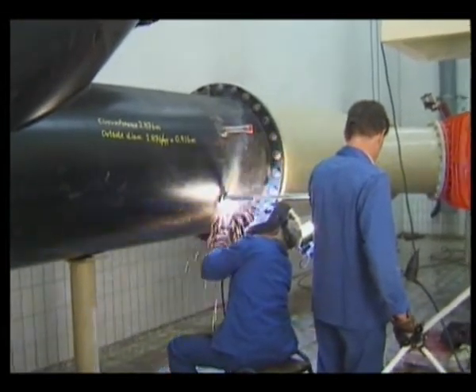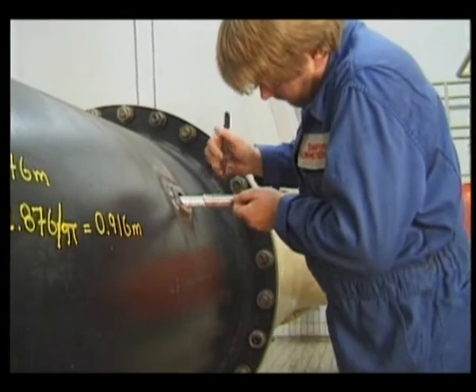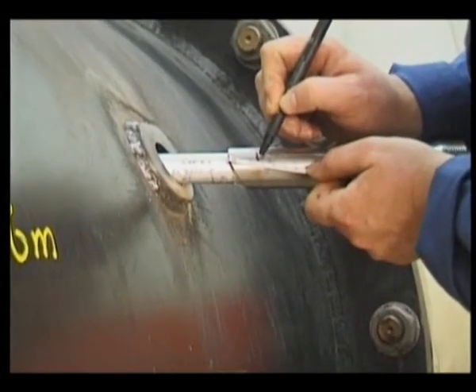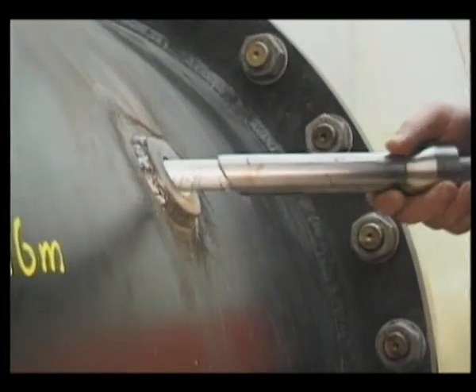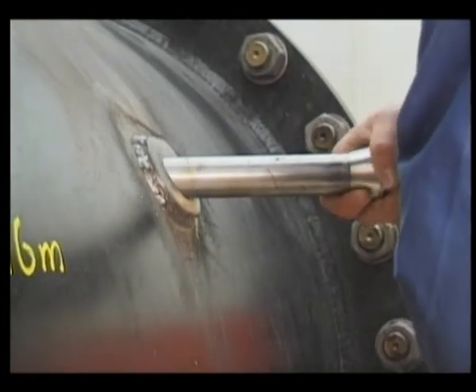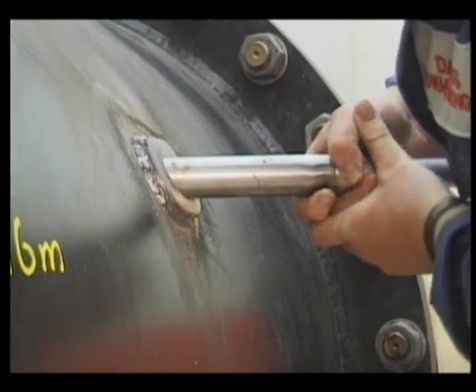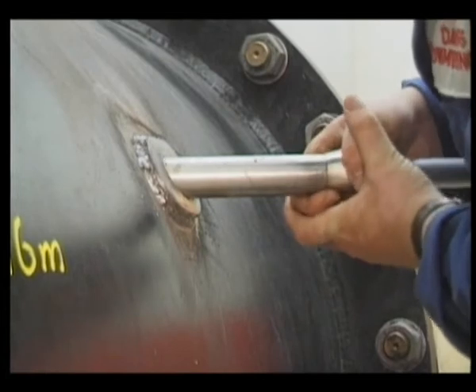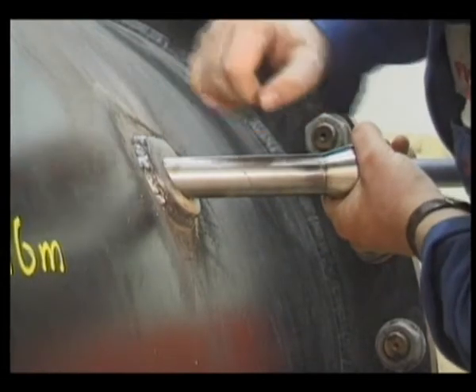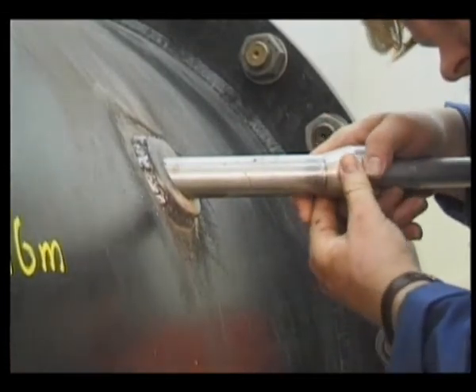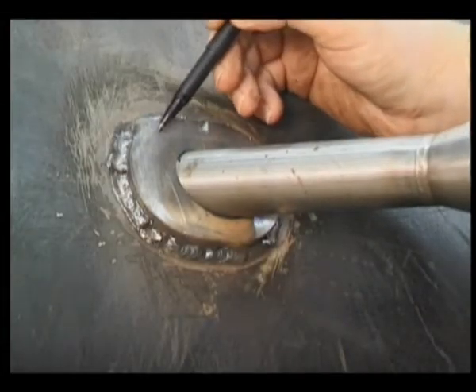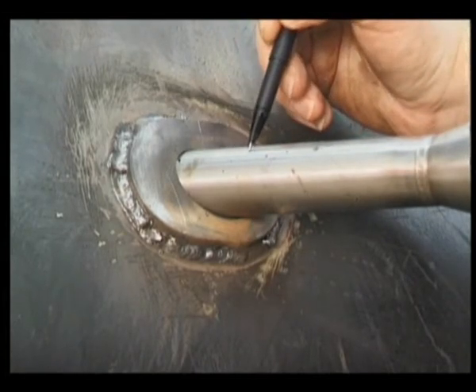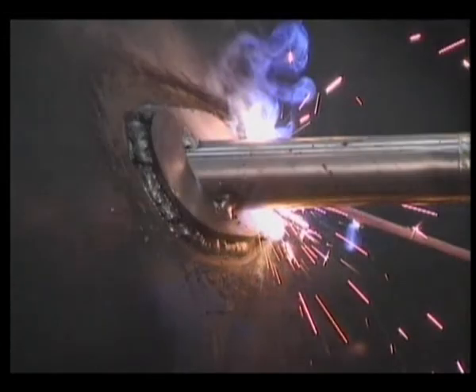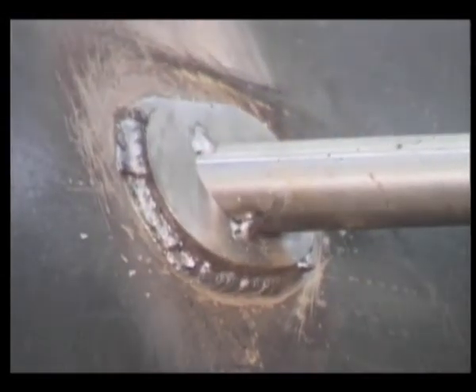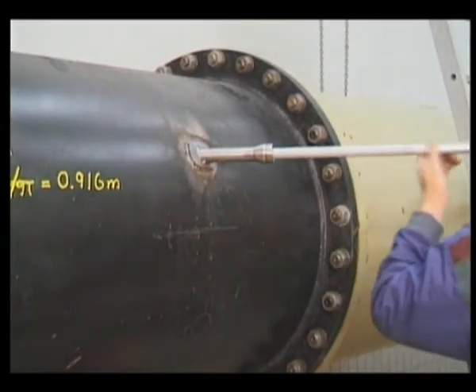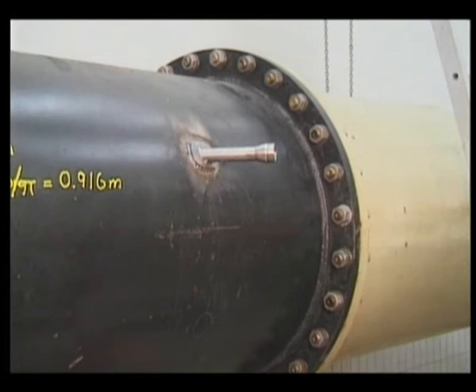The transducer holders must be led into the mounting plates and pipe until aligned with the internal pipe wall. To ensure this, a mark's drawn on the transducer holders. The diagonal line on the mounting plate must be aligned with the line on the transducer holders. Then the transducer holders are tack welded in 3 or 4 places. Don't forget to remove the alignment rod before you finish welding, otherwise it'll jam because of the heat from the welding.